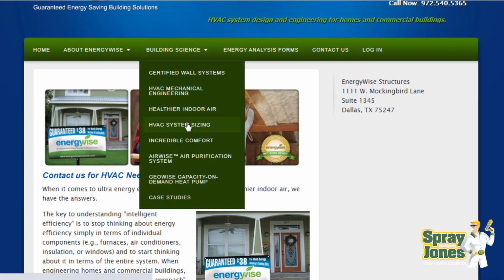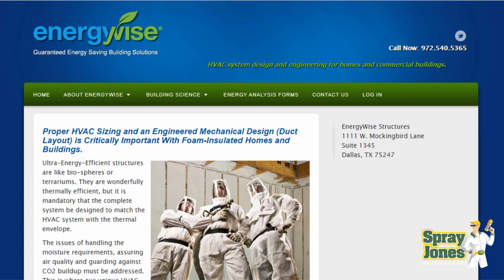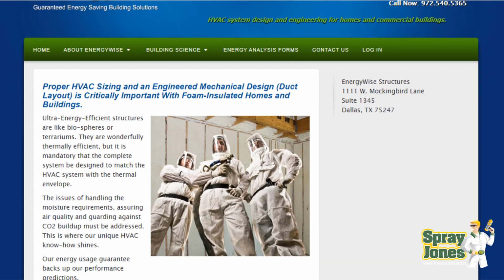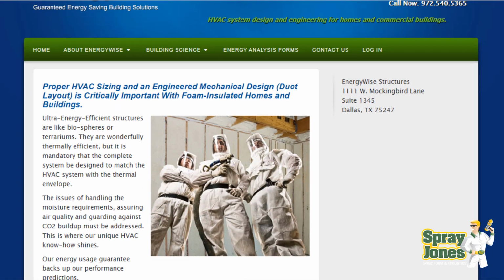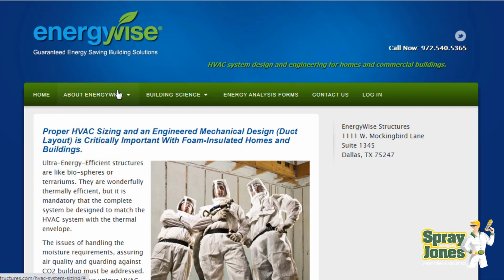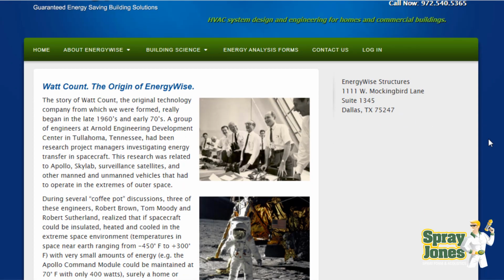They are a huge advocate of the spray foam non-vented attic system for the express purpose of having ductwork and mechanical equipment that can't otherwise go elsewhere in the structure, that needs to go through the attic space in order to be distributed, utilizing the non-vented, sealed, and conditioned attic space. But what they really do that is brilliant is they balance the humidity levels, they balance the cubic footage, they balance the BTUs and the tonnage necessary based on their modeling of load. And they take into account the direction of the face, the amount of windows, the square footage. So they have a very comprehensive understanding.